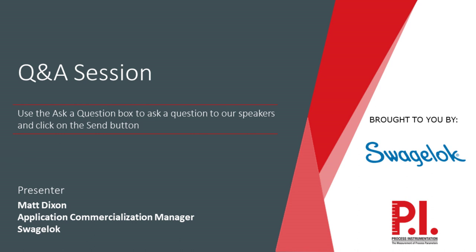Okay, thank you, Matt, for that answer. Our next question asks, does this sampler also test the ammonia for oil content? Okay, yeah. The answer to that is no. So for a little bit of background for those who don't know, there are generally two primary measurements that ammonia producers are worried about. One is the moisture, and the second one is the oil content that would typically come from the compressors in the process.